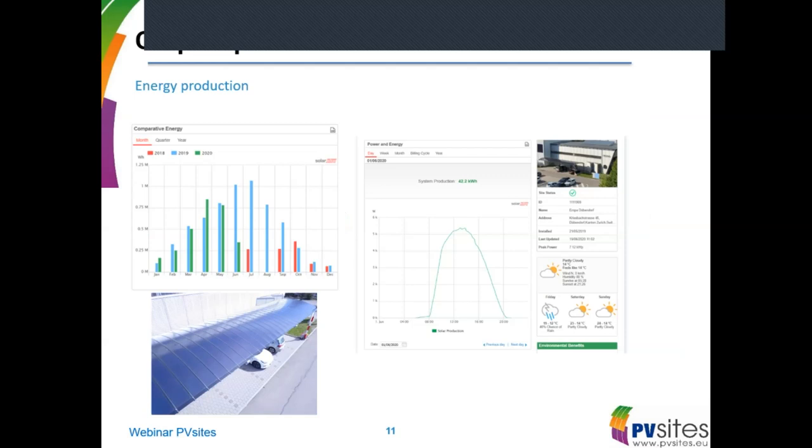So here, the production of this roof, I want to show you one thing. If you look in April, when the sun was still flat, and we had very good weather this year, you can see a lot more production. And this is due to this aluminium facade in the back. So we have a lot of reflection coming here to these modules that are actually bent towards the building. So here we have a very good situation where we can profit from surrounding light.